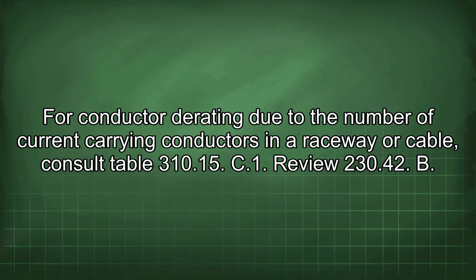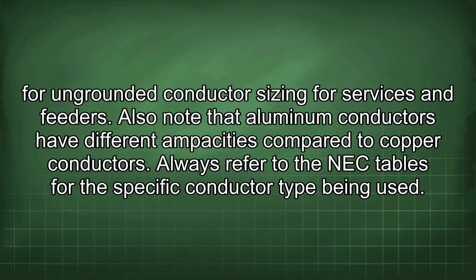Review 230.42(B) for ungrounded conductor sizing for services and feeders. Also note that aluminum conductors have different ampacities compared to copper conductors. Always refer to the NEC tables for the specific conductor type being used.